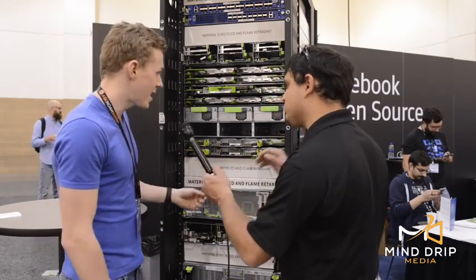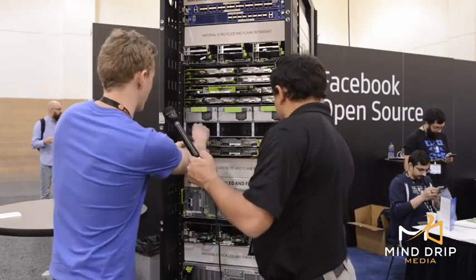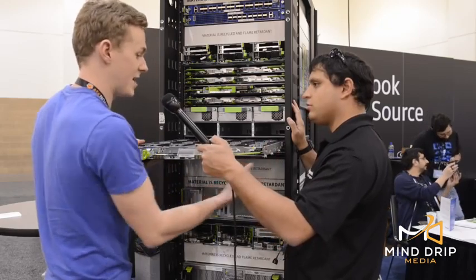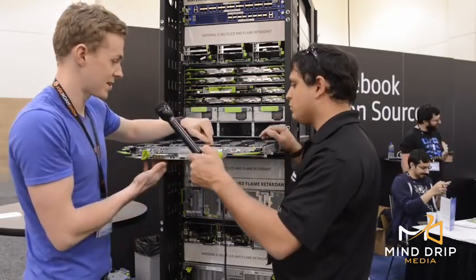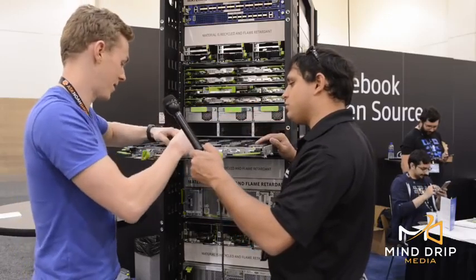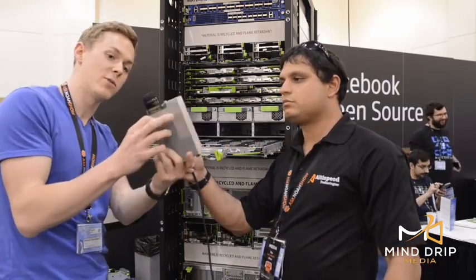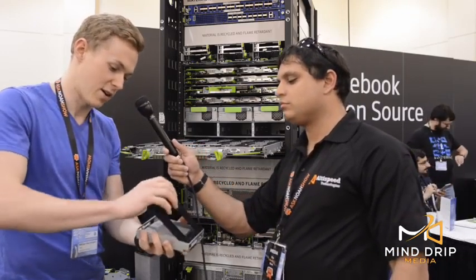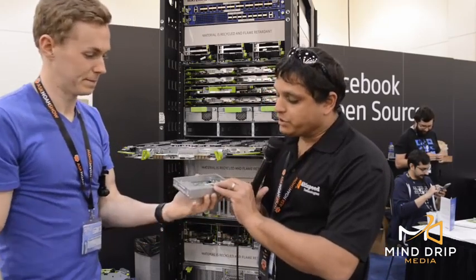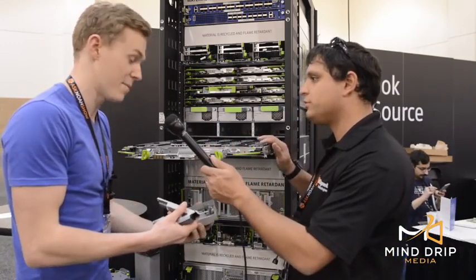The next sled is similar to the first but instead of SAS or SATA-based hard disks, this one is all NVMe — your newer tier of storage. It's five disks wide, 15 total. The disks use a similar but newer connector and there's a lot of metal for heat management. Each disk sits in a metal tray with a U.2-style connector on the back. You can take off the top piece to expose the inside and it fits standard M.2 drives. This sled is designed specifically for flash storage — and by the look of it, designed for very high heat-producing flash storage.